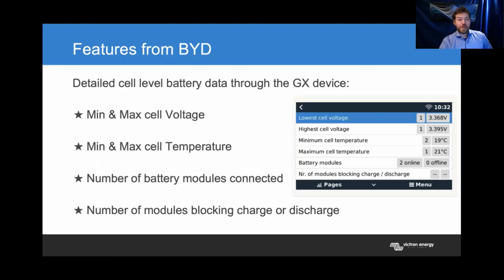One other improvement from the close collaboration between BYD and Victron is improved internal diagnostics. Now we get some cell level data coming out of the BYD battery onto the GX device, which is also communicated to our VRM online monitoring portal. You can see minimum and maximum cell voltages, minimum and maximum temperatures, the number of battery modules connected, which is very useful when commissioning a system, and if any individual module is blocking charge or discharge, maybe there's a fault. This is now also important because there's less diagnostics on the front of the module itself. I'll show you some photos in a second.